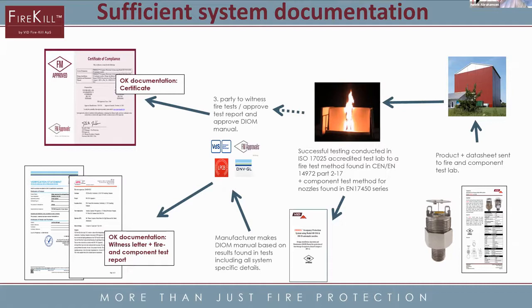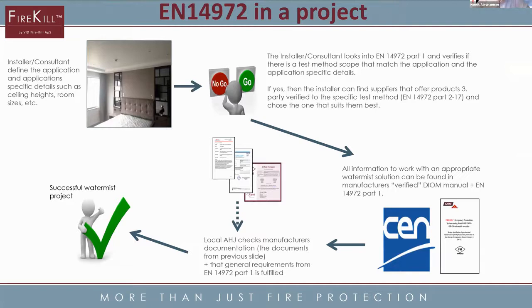This DIOM will be evaluated by a third party — could be FM Approvals, VdS, DNVGL, LPCB, etc. Then you get a certificate or a witness letter and a final component test report, and that way you are basically good to go. In a real project, the installer and consultant will look at what kind of application they have, then look into which parts they need. Then they can find the manufacturers of Watermist systems who can provide these codes. These manufacturers and the installer have to give the AHJ all the test reports, the certificates, etc. He evaluates whether this fulfills his requirements, and then you can start a successful Watermist project.